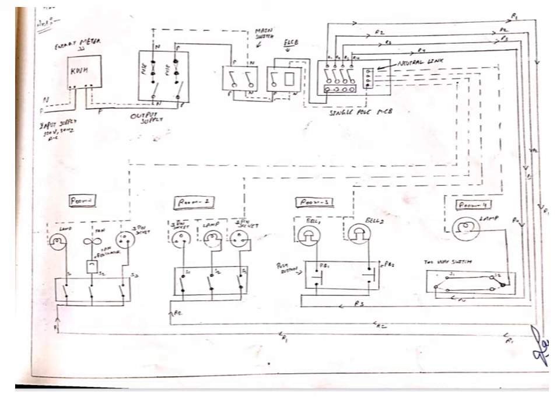First of all, there will be the energy meter. Neutral and phase are taken as input, and then neutral and phase are taken as output from the energy meter. The energy meter will measure the energy in kilowatt hours. So it will measure the units consumed by us, and accordingly the bill will be generated. Then this output from the energy meter will go into the main switch, the main switch for the whole installation. So this is the main switch, phase and neutral.